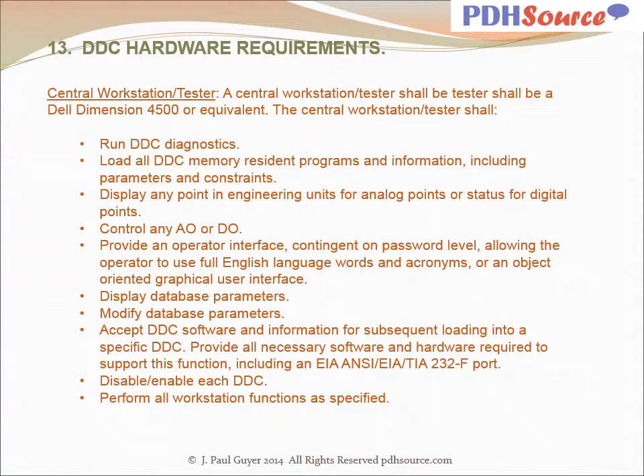The central workstation tester shall be a Dell Dimension 4500 or equivalent. The central workstation tester shall run DDC diagnostics, load all DDC memory resident programs and information, including parameters and constraints, display any point in engineering units for analog points or status for digital points, control any AO or DO, analog output, digital output, provide an operator interface contingent on password level, allowing the operator to use full English language words and acronyms, or an object-oriented graphical user interface. Display database parameters, modify database parameters, accept DDC software and information for subsequent loading into a specific DDC, provide all necessary software and hardware required to support this function, including an ANSI 232F port. Disable, enable each DDC and perform all workstation functions as specified.